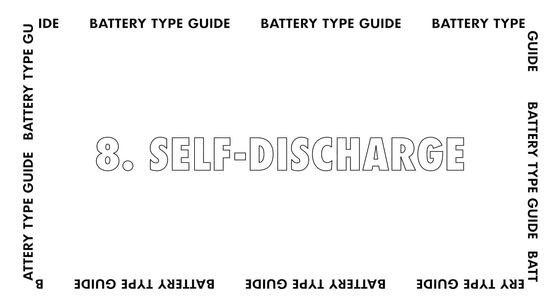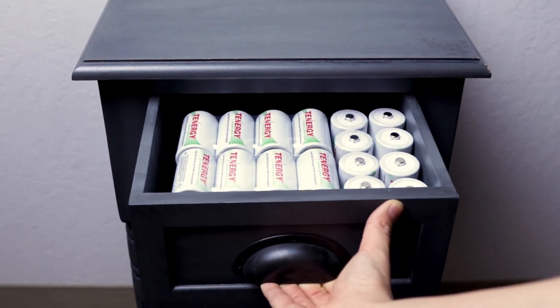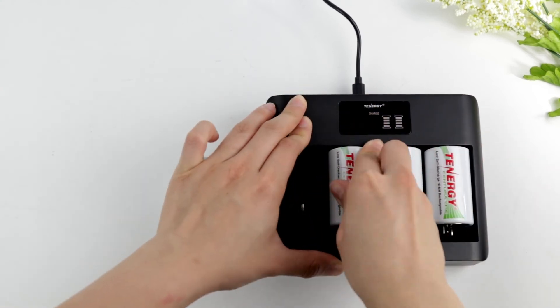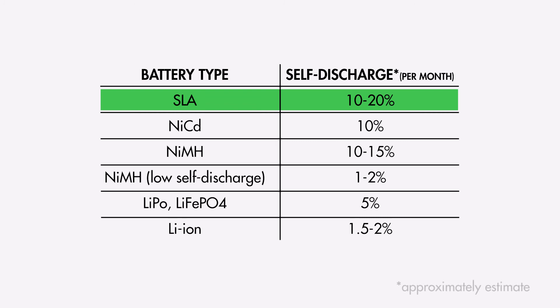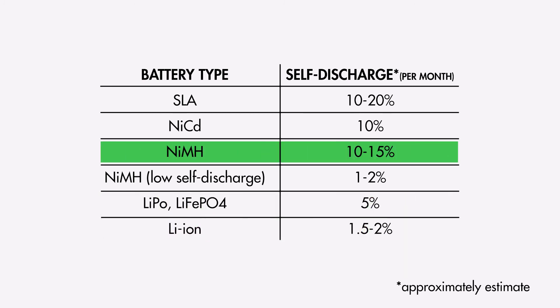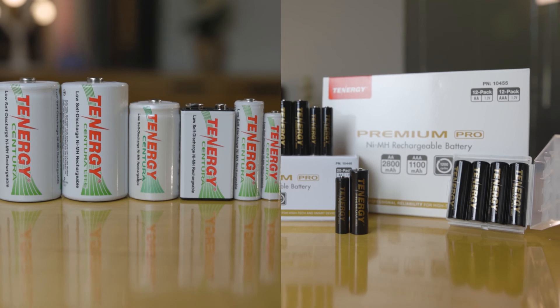The last difference is self-discharge rate — the amount of energy lost over time during storage. It's related to maintenance frequency: the higher the self-discharge rate, the more often you'll need to recharge the battery to avoid over-discharging during storage. Sealed lead acid batteries have a high self-discharge rate of about 10 to 20% per month and shouldn't be discharged over 50%, so recharge every 4 to 5 months. Lithium-based batteries have a self-discharge rate of around 1.5 to 5%. Some nickel metal hydride batteries have a high rate of 10 to 15% per month, but with newer technology, low self-discharge NiMH batteries — like the Centura and Premium Pro batteries — lose only around 15% of capacity per year.